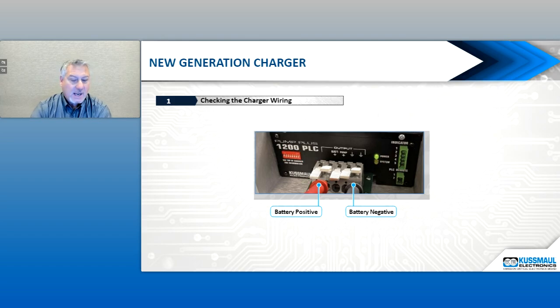I had an example where a local department contacted me multiple times about the charger not working, so I went to visit them. Turned out someone installed a radio, and when they did, they needed a ground, so they took the ground off of the charger and used it for the radio. That's one of those things that checking the wiring first would have revealed - it was missing a ground. I connected the ground, and the battery started charging, no problem. So the first thing to do is check the wiring.